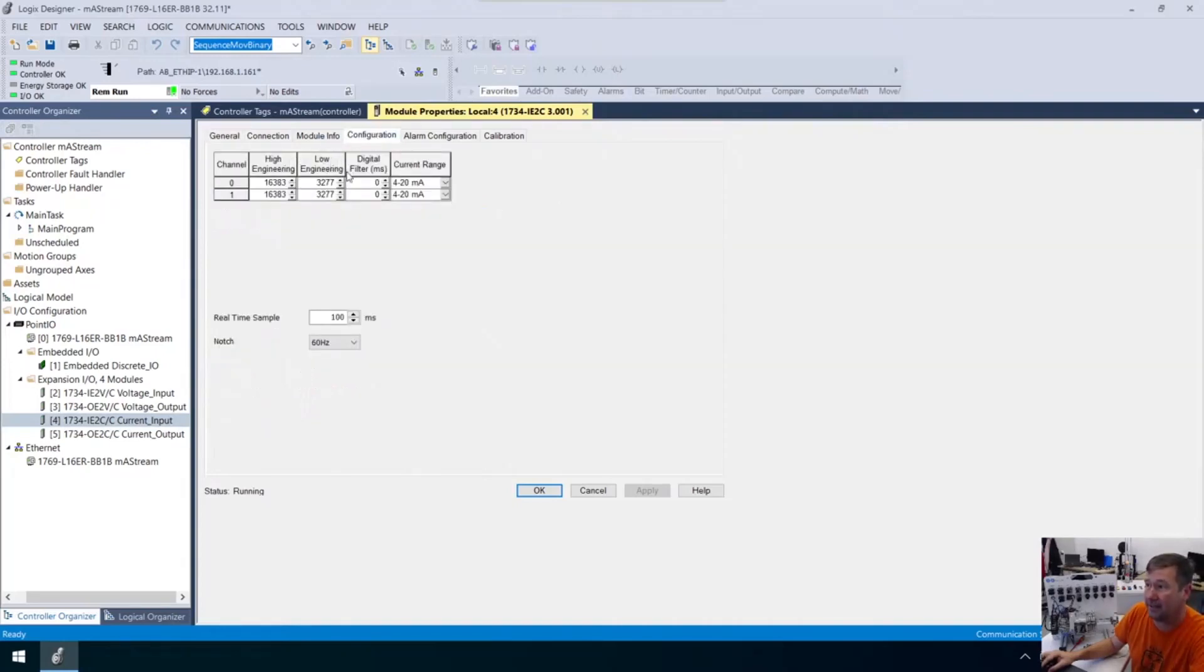And if we look at it, here it is. Our low engineering is 3277, and our high engineering is 16,383. Now, this is one of those that we need to do a little math on. And I know a lot of times when I start saying math, I get glazed over looks. But really, if we walk through this slowly, then I think we can do it. And hopefully, I have enough of what we need down here to walk through this math.